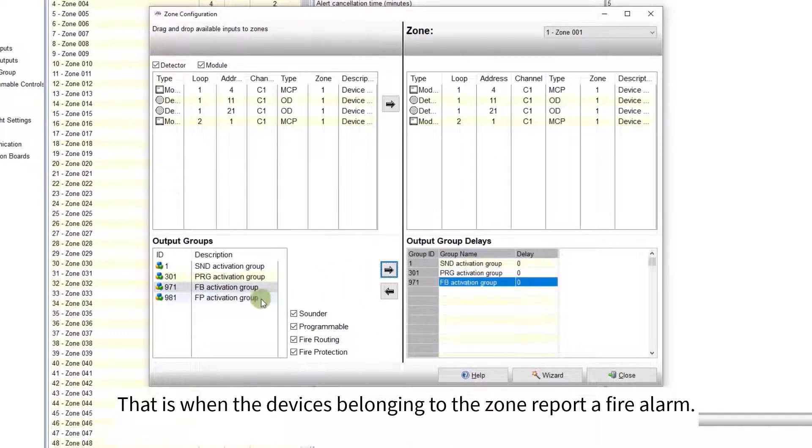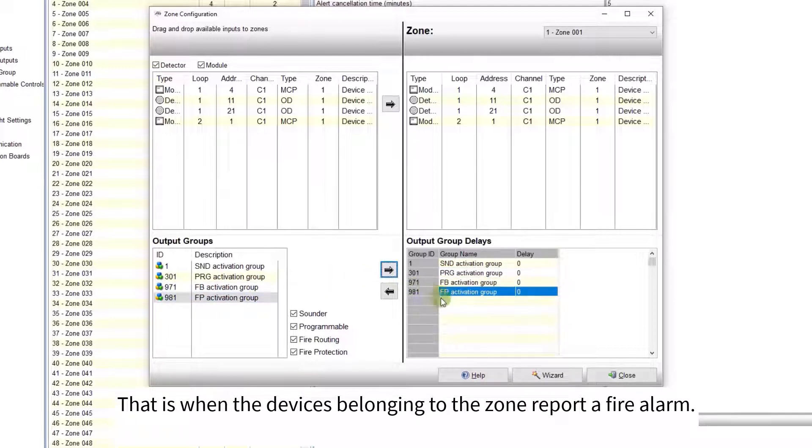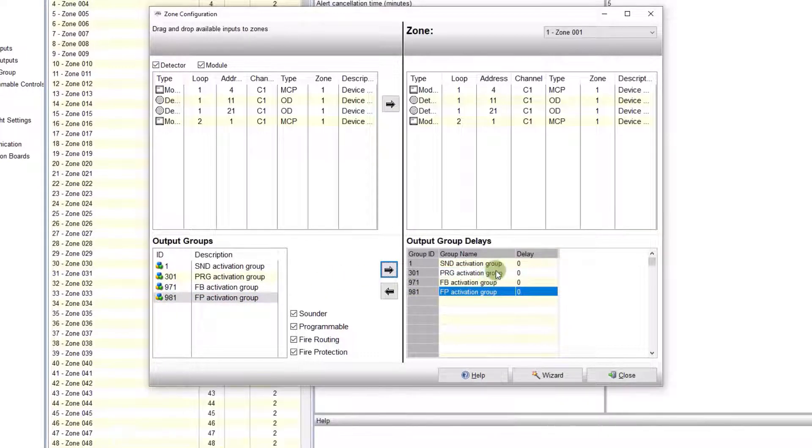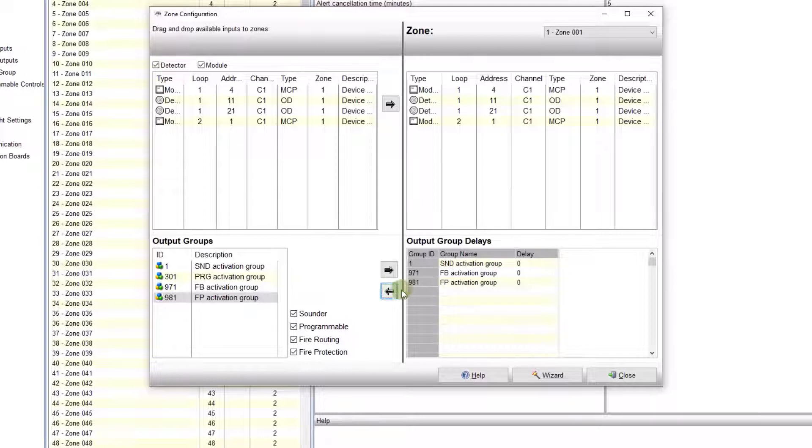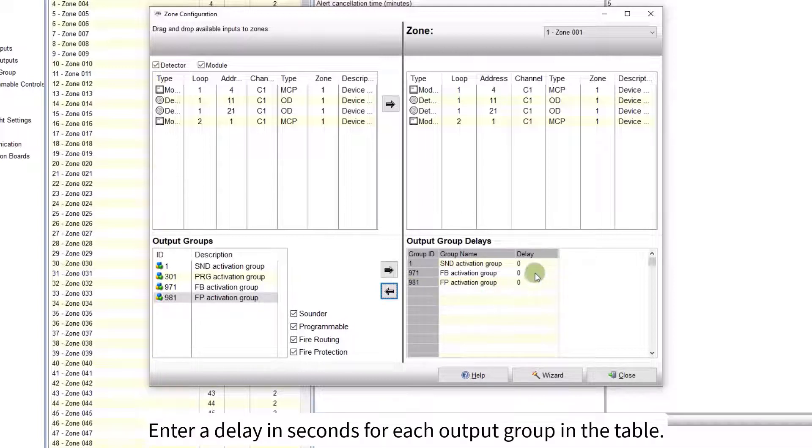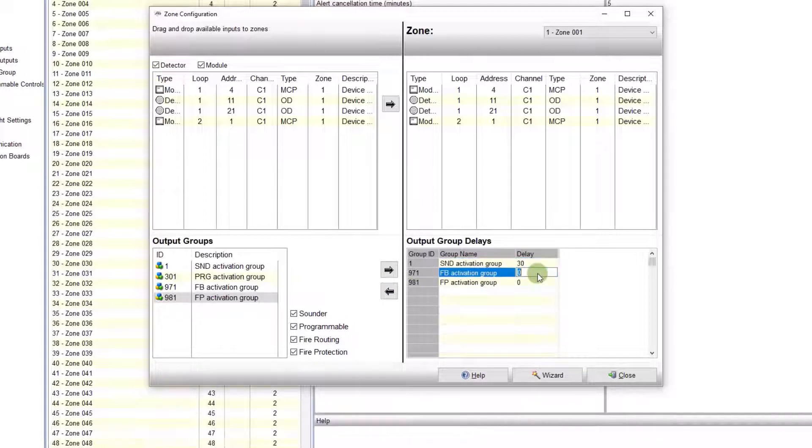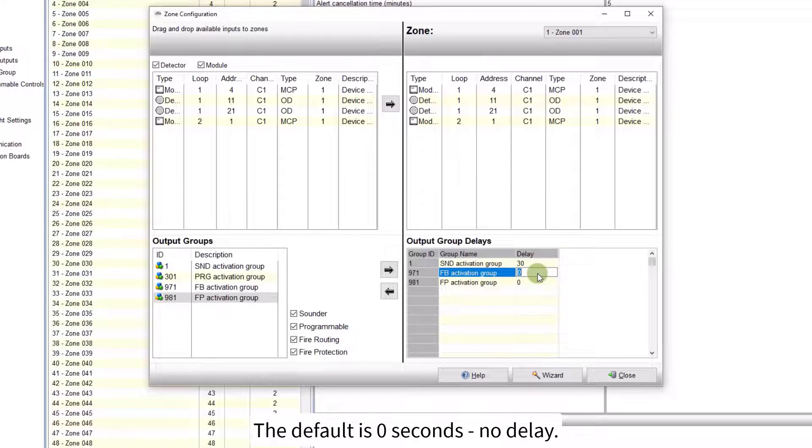That is, when the devices belonging to the zone report a fire alarm. Enter a delay in seconds, for each output group in the table. The default is zero seconds, no delay.